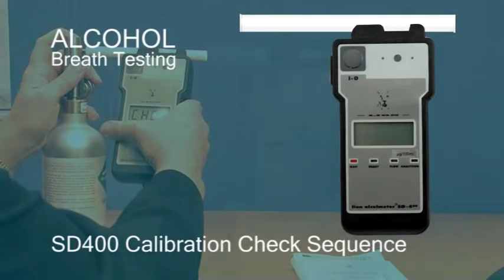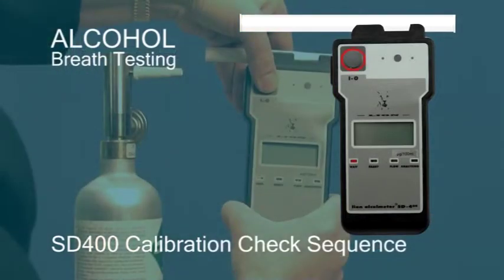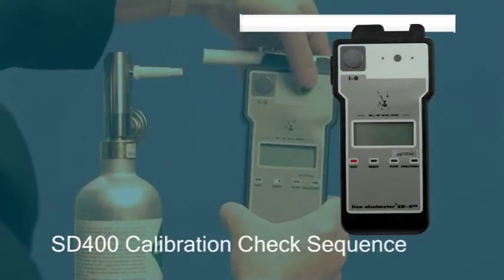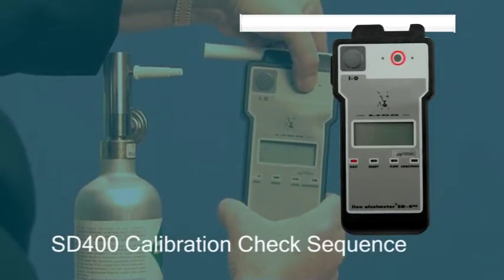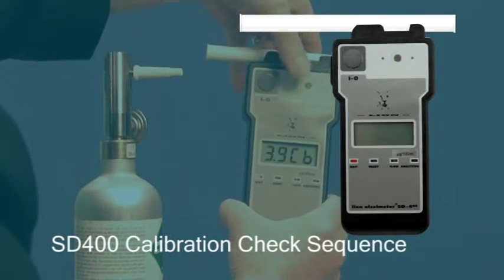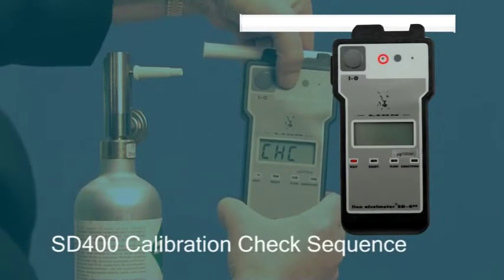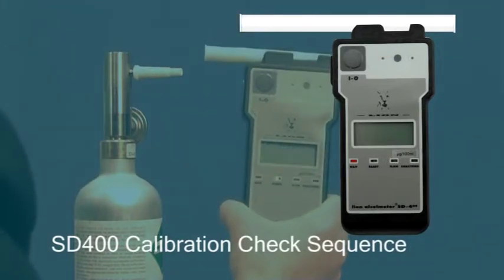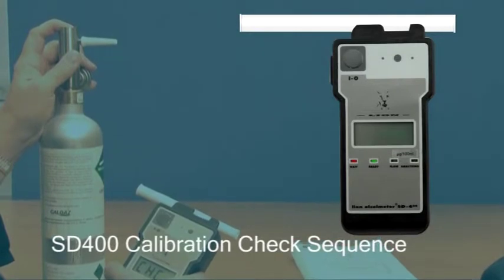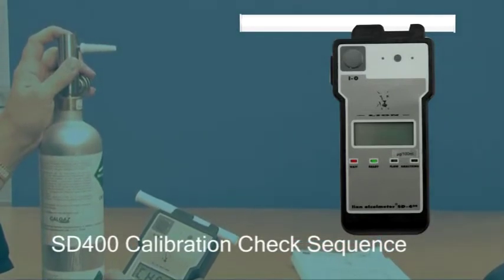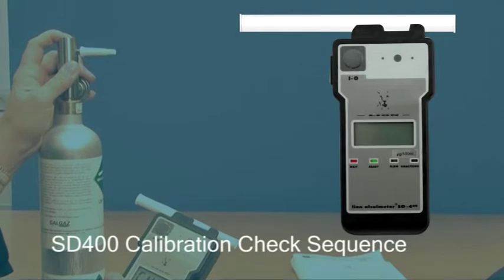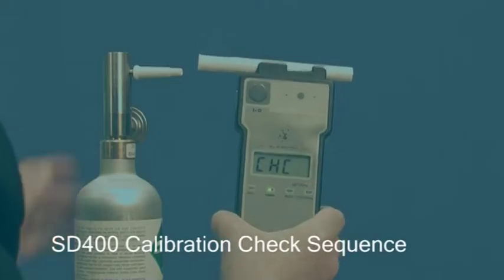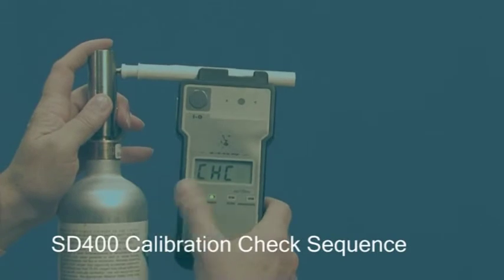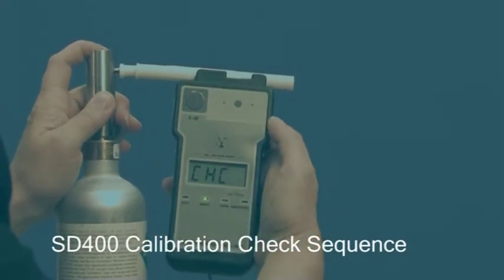SD400 calibration check sequence. Switch the instrument on, and before the diagnostic sequence is completed, press and hold down function switch C. When a continuous tone is heard, release C and press and release function switch B. Wait for the ready light. Hold down function switch on top of cylinder for 5 seconds to clear any air that may have collected in the valve. Use the connector tube with a mouthpiece and fit this to the gas cylinder and the SD400.